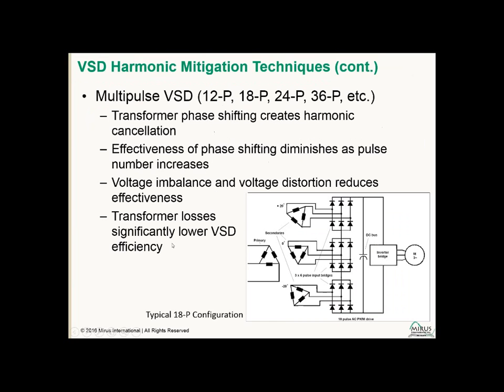Many applications will look at multi-pulse drive systems, 12, 18, and so on. Those introduce transformer phase shifting strategies to create harmonic cancellation. One thing to note is that the effectiveness of phase shifting diminishes as we get into higher pulse numbers. That's because the phase shifting is dependent upon the phase angles of the harmonics being similar on each of the different rectifier sections of your multi-pulse drive.